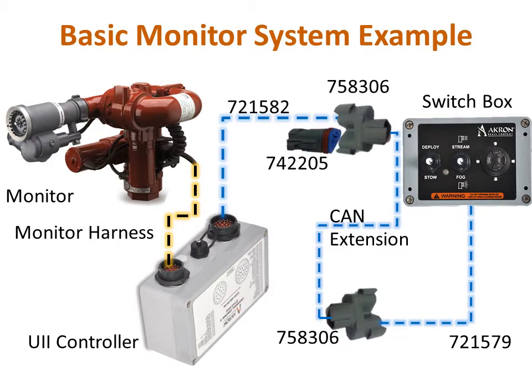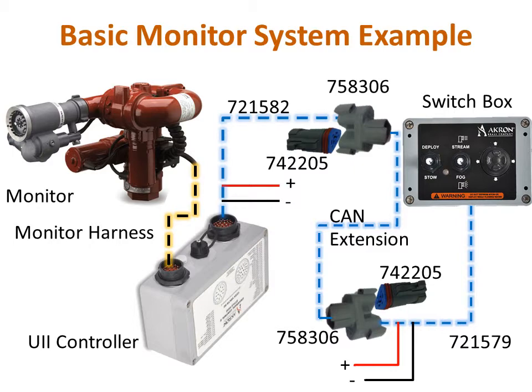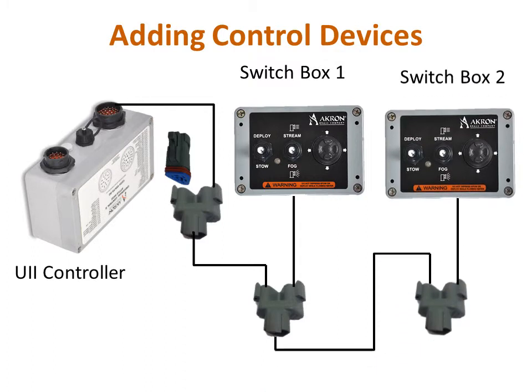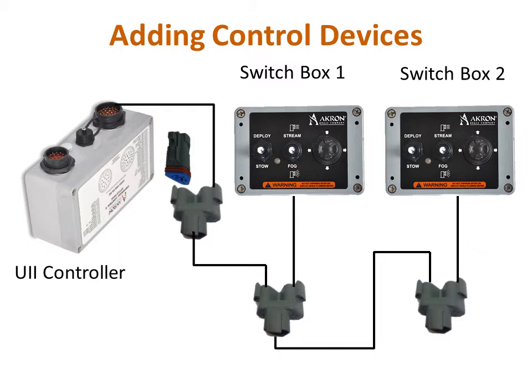Next, add one terminator plug at each end of the network. Finally, make the power and ground connections to the UII controller and the control input devices as required. Additional devices can be added to the network by removing a terminator plug and inserting a new device T connector and extension cable, then reinstalling the terminator on the new device T connector.